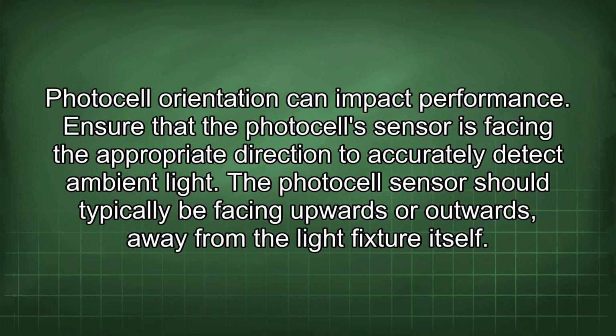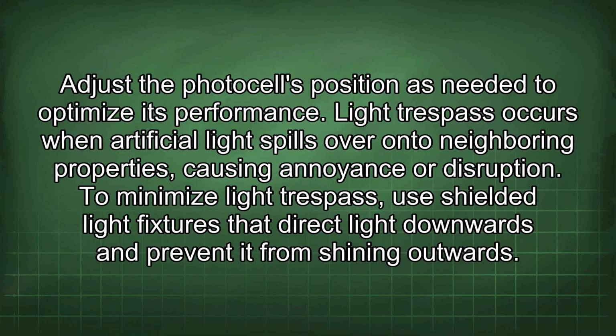Photocell orientation can impact performance. Ensure that the photocell sensor is facing the appropriate direction to accurately detect ambient light. The photocell sensor should typically be facing upwards or outwards away from the light fixture itself. Adjust the photocell's position as needed to optimize its performance.